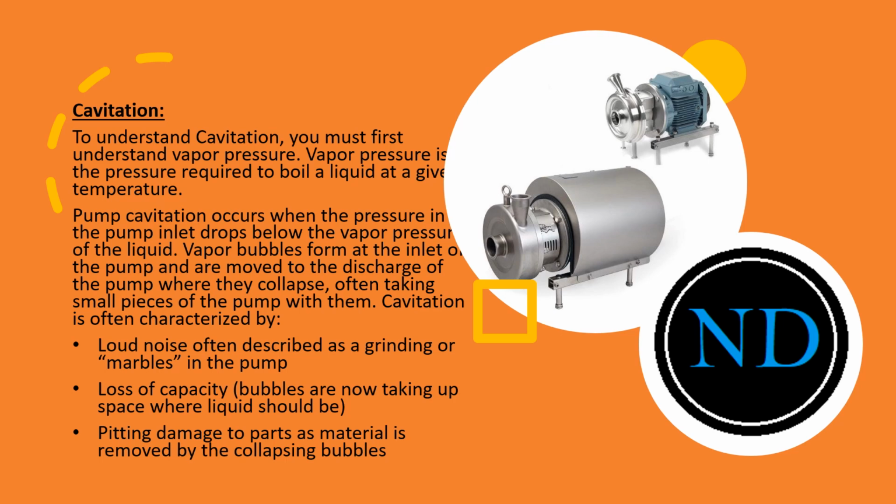Secondly, loss of flow, meaning capacity, you are not getting the proper capacity. It also indicates that you are not getting the proper suction. Third one is damage to the pump due to the air traps, bubbles inside the pump. It will damage your pumps and some impellers. Basically this happens because there should be water inside the pump, but instead there is a water plus air mixture.